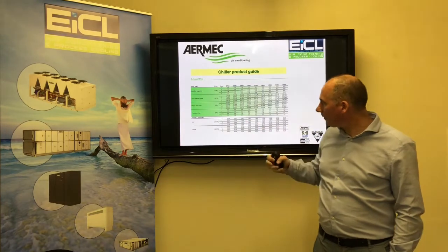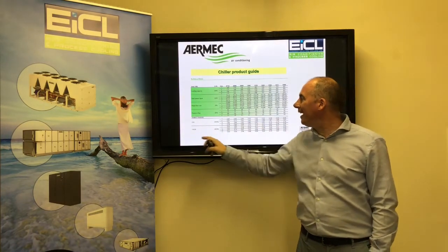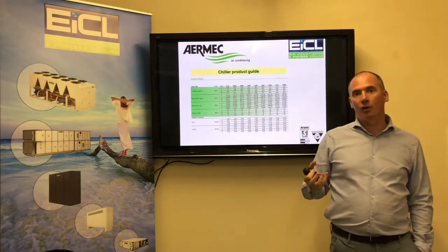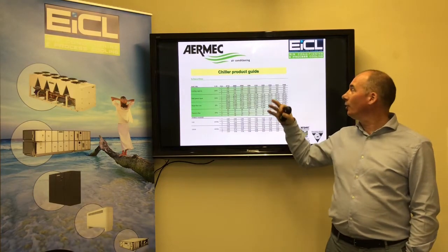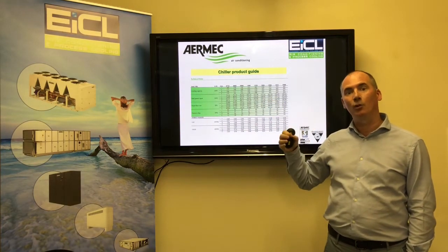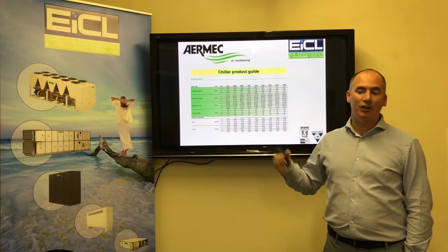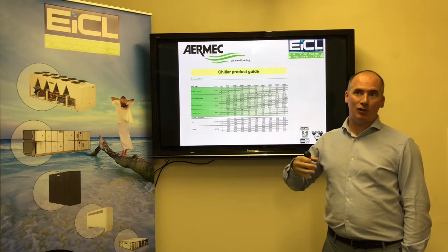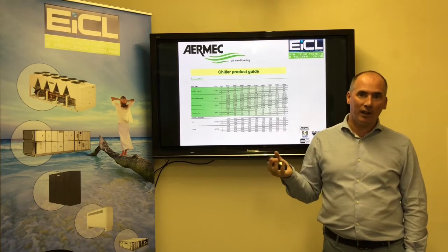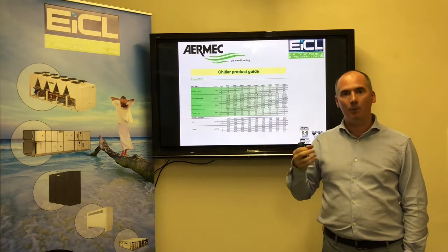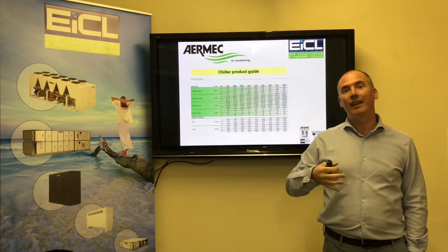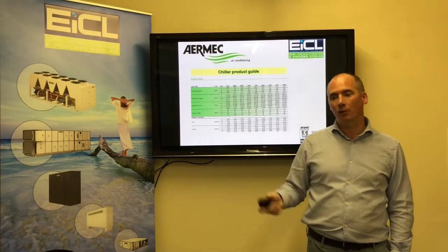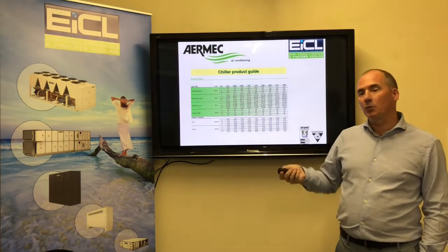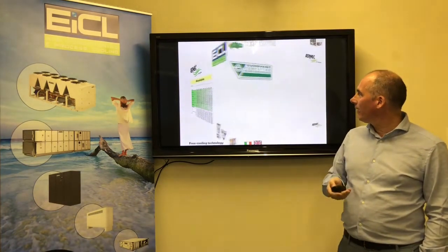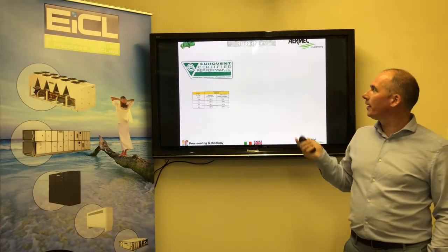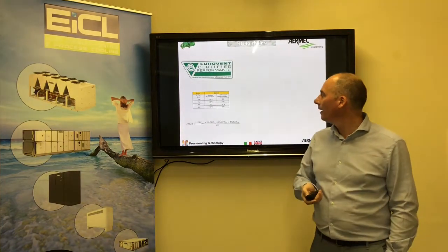There is also a formula, ESEER, which is much more relevant because your EER, like I said, is only relating to when you're running at 100% load. And chillers are typically sized to operate at the hottest day of the year, solar heat, bodies in the building, lighting and so on, and they rarely ever run at 100% load. So the ESEER is a much more realistic figure. It's a calculation, it's a Eurovent approved calculation.